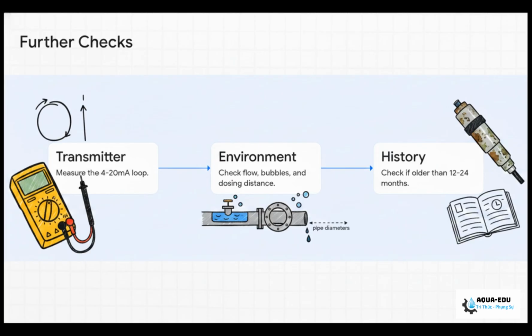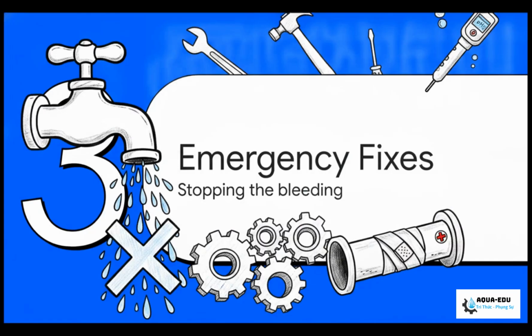And finally, step 7. Check your maintenance logs. Honestly, if that combo probe has been soaking in industrial wastewater for over 18 to 24 months, it might have simply aged out. Nothing lives forever. Which brings us to sections 3 and 4, emergency fixes, cleaning, and calibration.